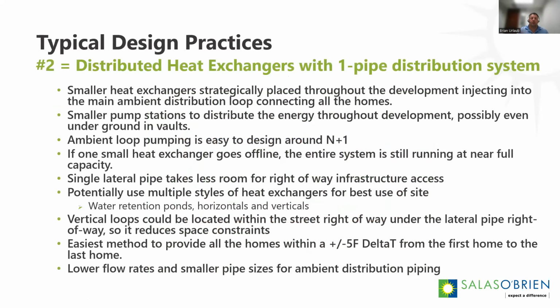So what I'm going to talk about is single pipe distribution. This lends itself to be more attractive for community type systems, because if you're putting it in the street with other utilities, you're only dealing with one extra pipe, and that pipe becomes smaller since it's not about providing everybody the exact same temperature. It's more about the temperature profile between every connection and energy source. It's also easier to design around N+1 or resiliency with additional pumping, loop fields, and energy sources.